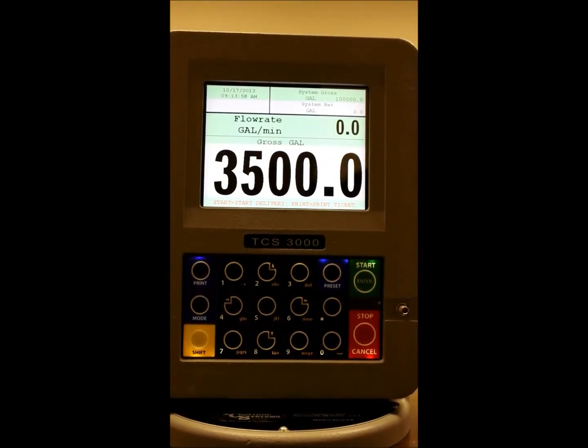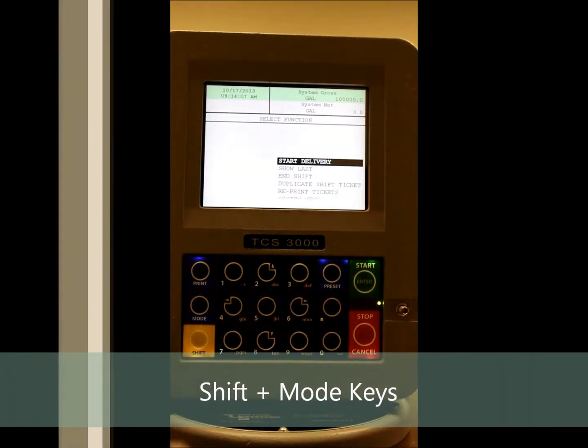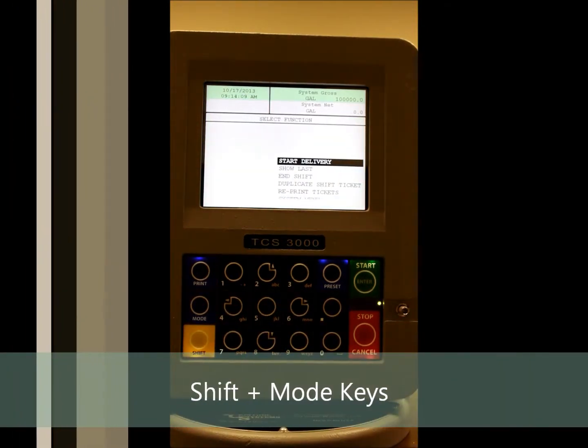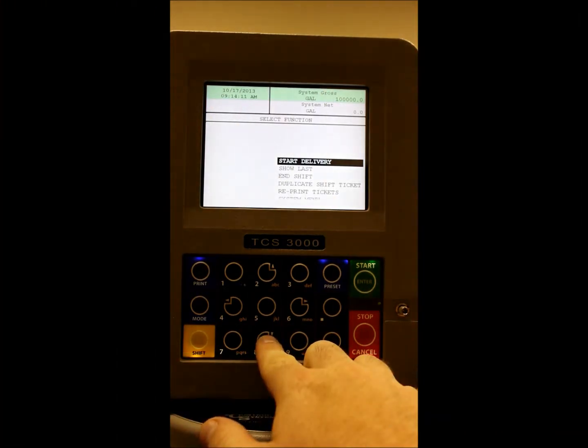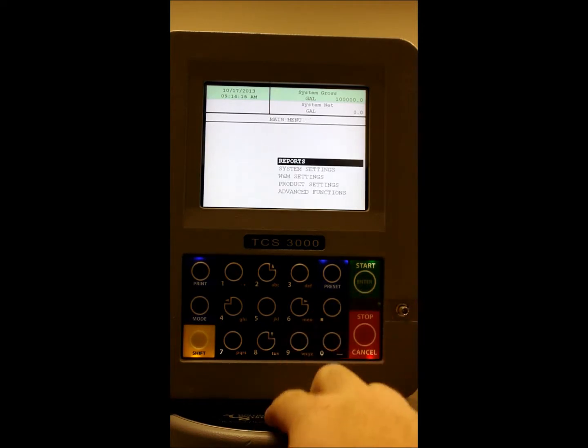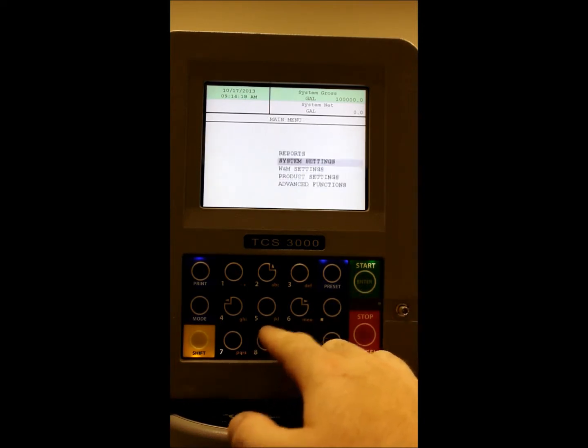Once you've backed out the calibration screw, we will need to access the system menu. To access the system menu, you'll push and hold down the shift key and mode key. This will allow you to go into the menu. We will use the navigational down arrow to scroll down to system menu and then to W and M settings.